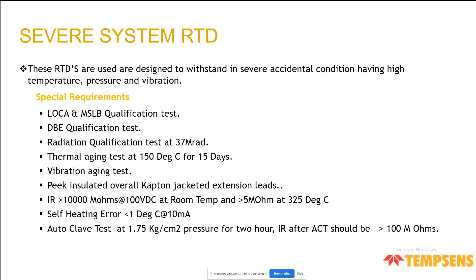Then we supplied to the PFBR reactor in India at South Bhavini. These were used in the sodium pipelines. We supplied the heaters also for these pipelines. So these were temperature sensors, 3 mm diameter, type K and type N. Both we supplied. Outer sheath of 316 and Inconel, rated for 1000 degrees centigrade, more than 5000 megaohm, with class 1 accuracy, and with a LEMO connector. And there were a lot of requirements, like we had to do radiography and other tests for this customer. They were again as per ASTM E235, the mineral insulated cable for this.